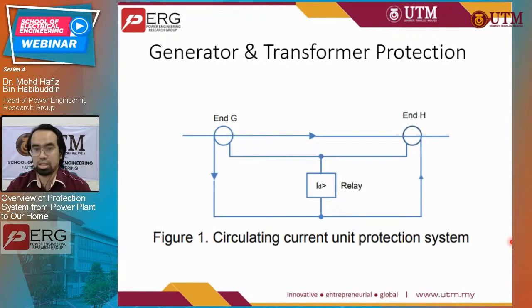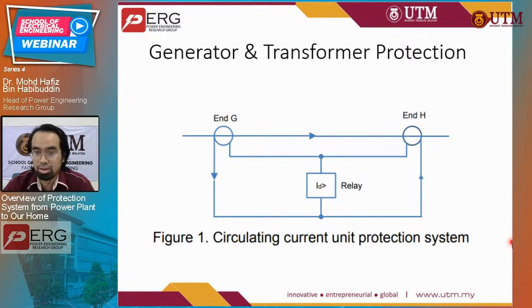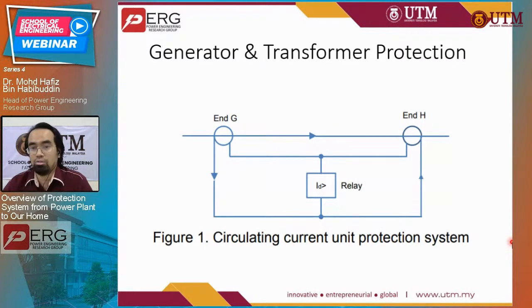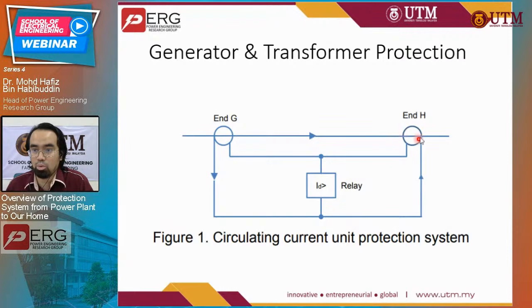I'll start by discussing generator and transformer protection — how the transformer and generator are protected. If you have an electrical engineering background, you know Kirchhoff's current law: current going in must equal current going out. With that, we measure the current that goes into the equipment — in this case generator or transformer — and the current that comes out. If the currents agree, it means it is working under good condition with no fault. If the input and output do not agree, it indicates a faulty system.